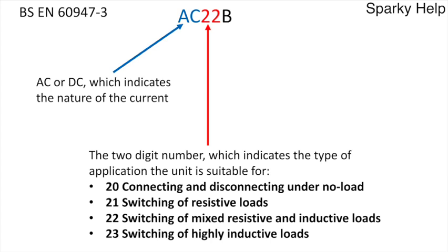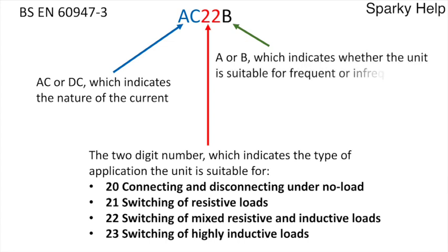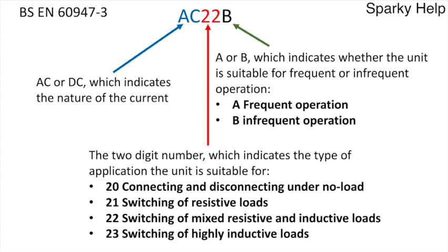If you look at a switch that says 20 on it, it's connecting and disconnecting under no load — so that is a pure isolator. If you see AC20, it is an off-load switch and you probably wouldn't want to see it as a main switch within the installation, because you'd want to be able to turn it off in an emergency. The final letter — A or B — means frequent or infrequent operation. You'd have to go to the manufacturer for their definition, but it could be many hundreds if not thousands of operations difference between each one.